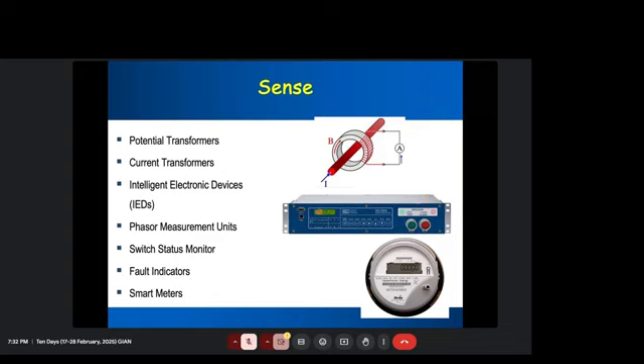You can use the same device for distance protection. You can use the same device for, say, over current relay. Typically an RTAC, which is an automation controller, will collect a number of currents and measurements from these protection or measurement devices, and can work like a microgrid management system, or like a relay coordination scheme. All those things are possible. The main thing is that it all has a processor or multiple processors.